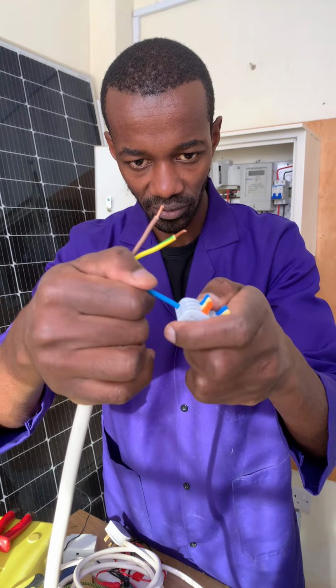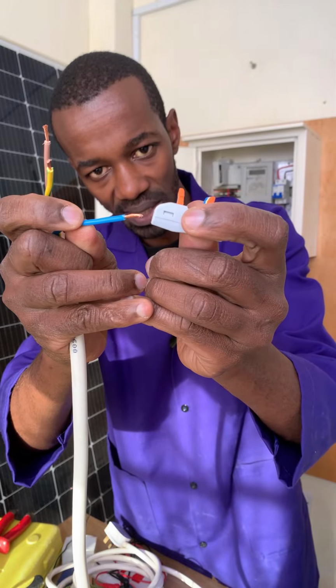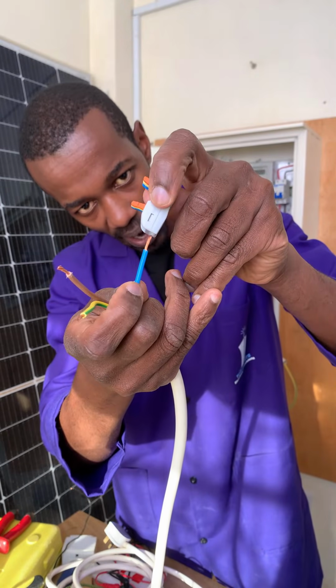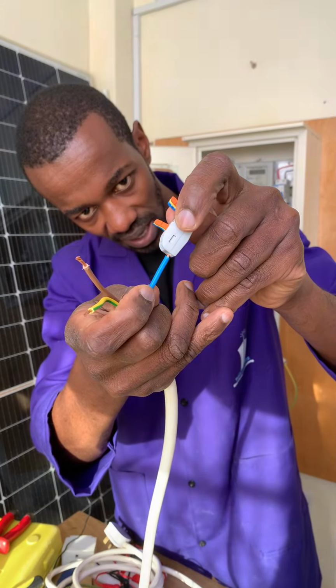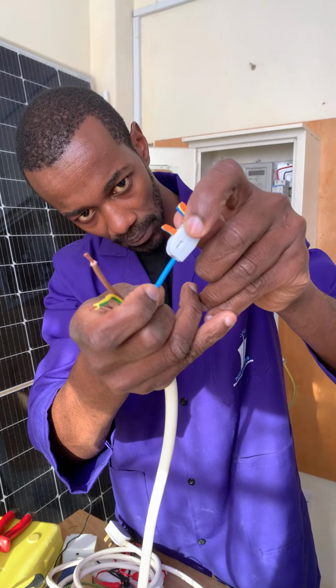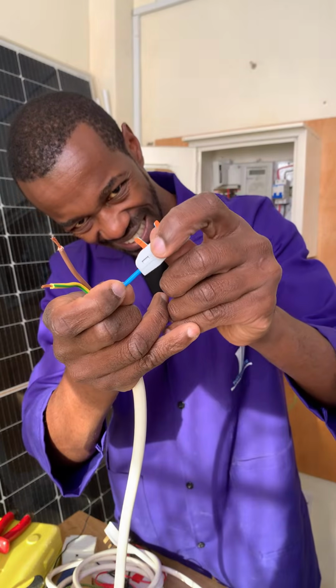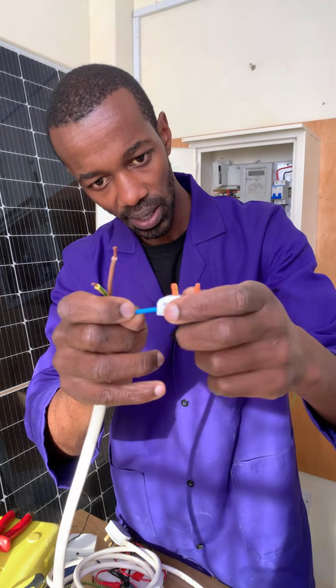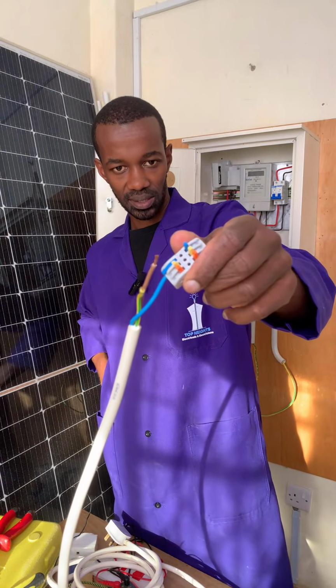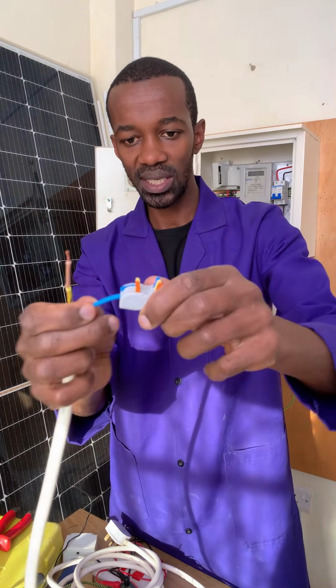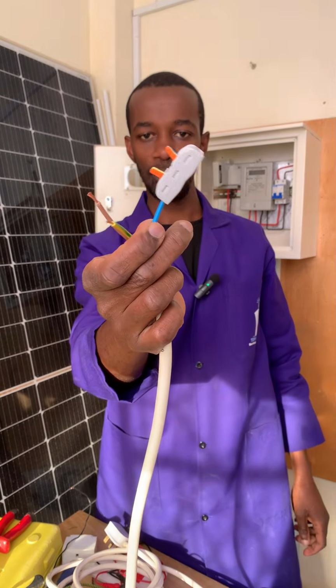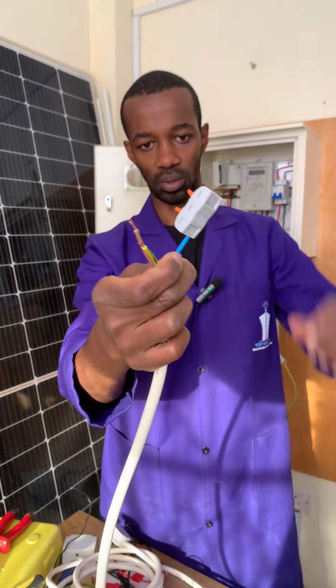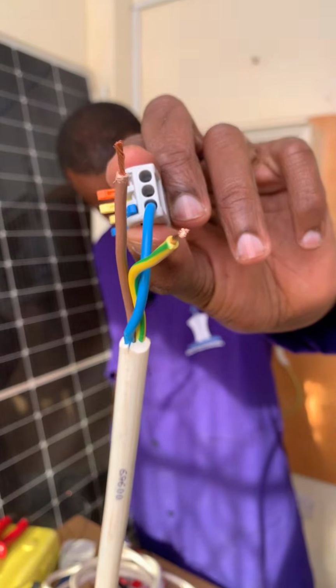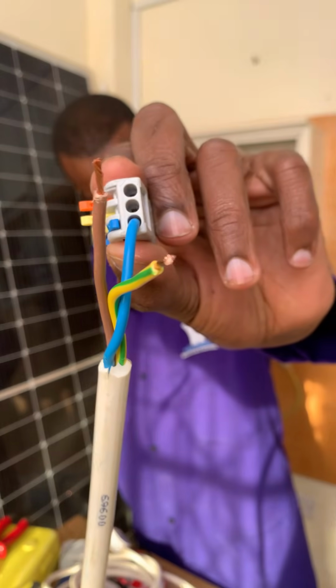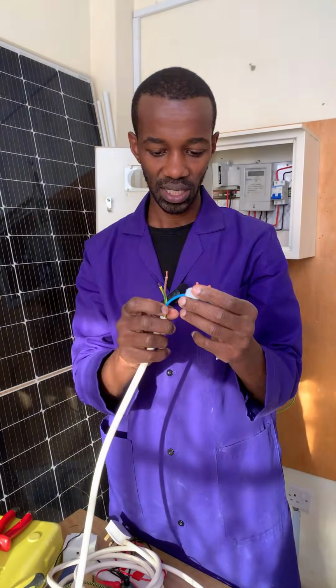I am always grateful. So what you notice is that once we insert the wire inside the WAGO, that is not the maximum point. We can still insert it further, and then we can return that lever, so we are sure that it is actually clipping on the wires and not the insulation. Very tight, but a very important point to note is that the wire is totally or completely inside, so it does not short circuit the other.